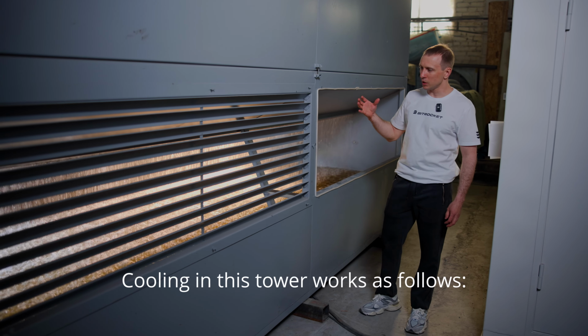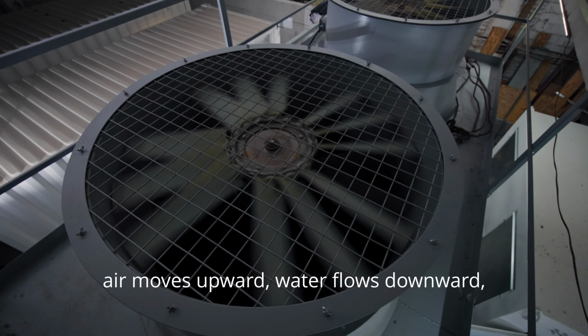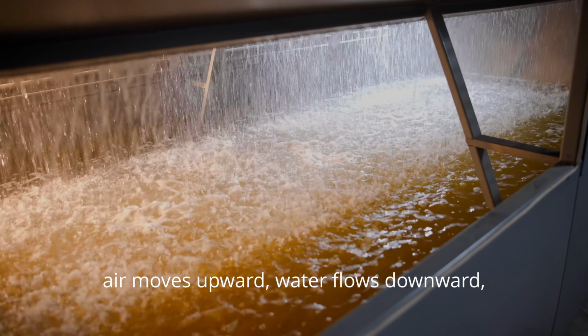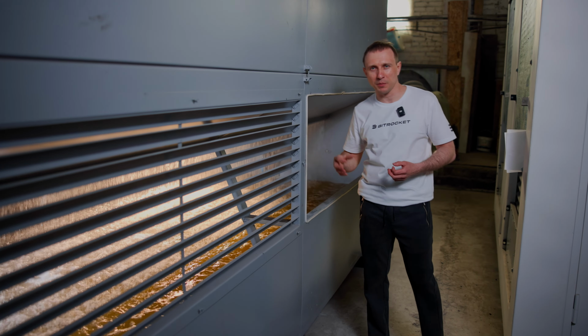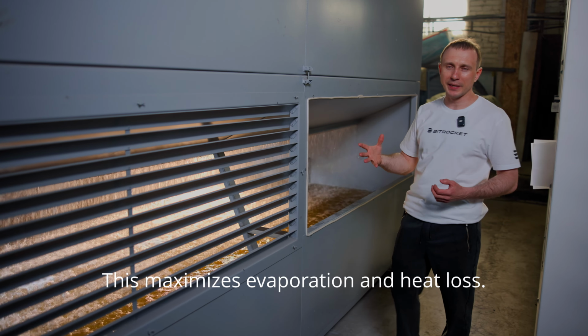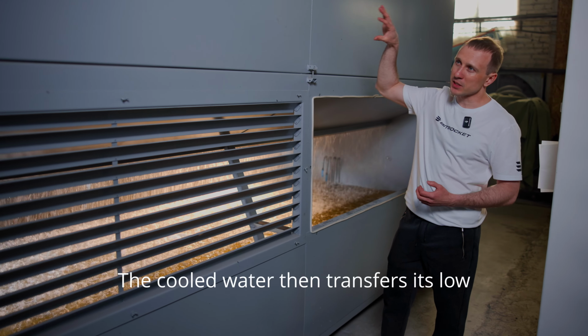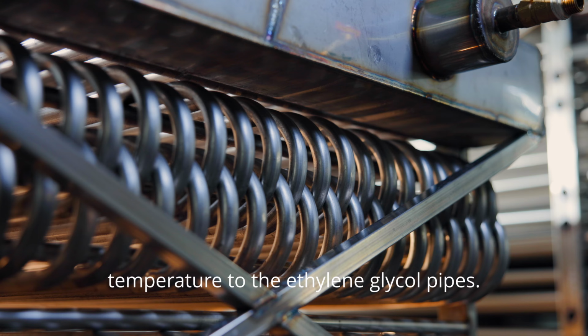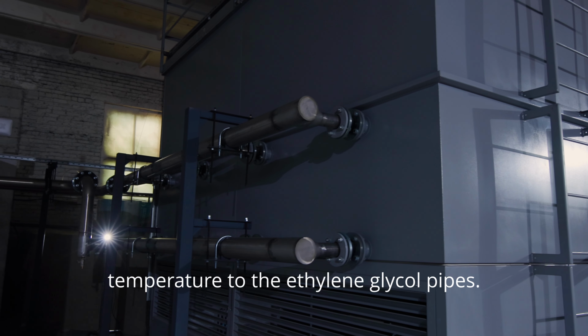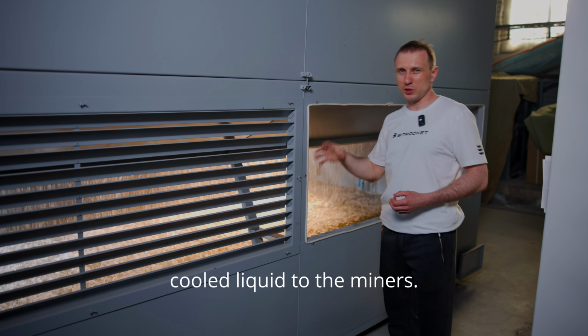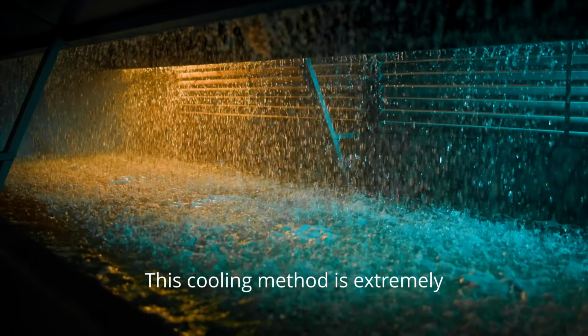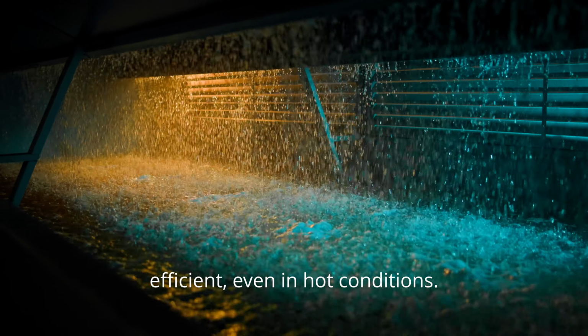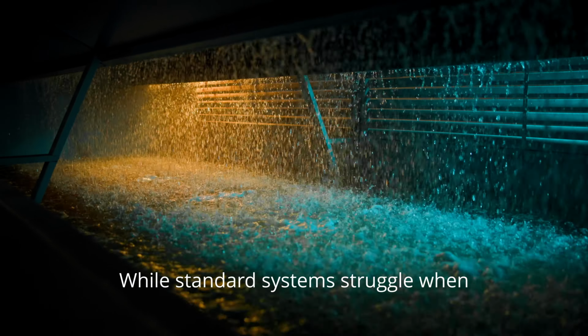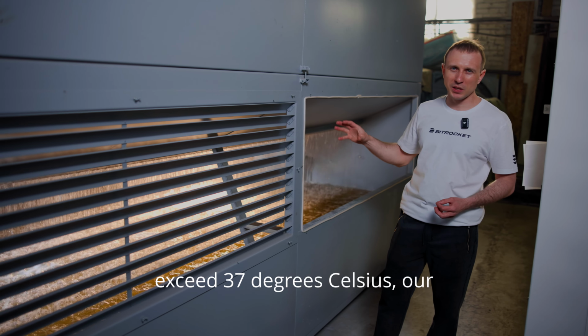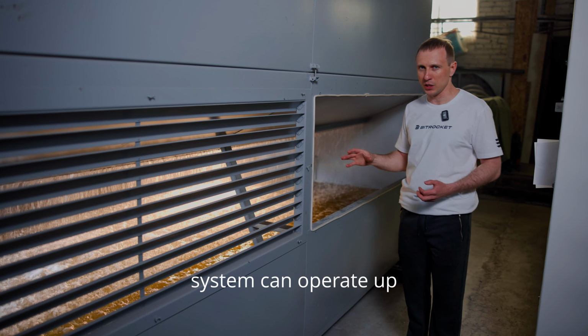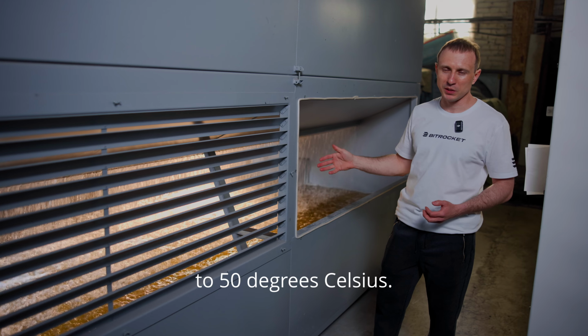Cooling in this tower works as follows. Air moves upward, water flows downward, creating a counterflow. This maximizes evaporation and heat loss. The cooled water then transfers its low temperature to the ethylene glycol pipes. That in turn deliver cooled liquid to the miners. This cooling method is extremely efficient, even in hot conditions. While standard systems struggle when ambient temperatures exceed 37 degrees Celsius, our system can operate up to 50 degrees Celsius.